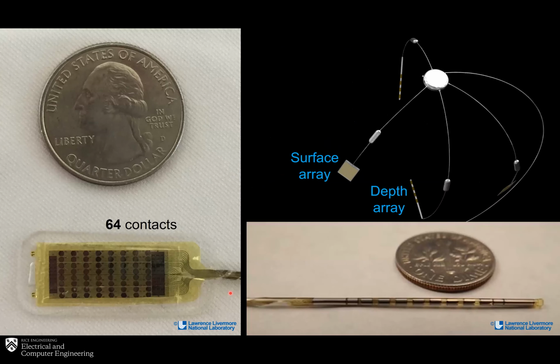These are the electrode arrays that are built at Lawrence Livermore National Labs, and it's equivalent of throwing away paper map and using Google Maps for navigation when it comes to higher density access to the brain, and going away from 4 contacts, which is kind of continent level access, to 64 contacts per lead. So we have both cortical leads as well as depth leads. So these are 4-way split contacts that allow us to do current steering and very complex stimulation patterns.